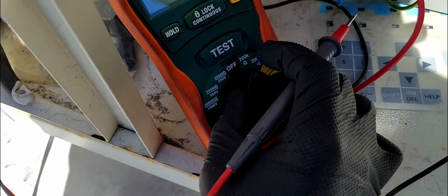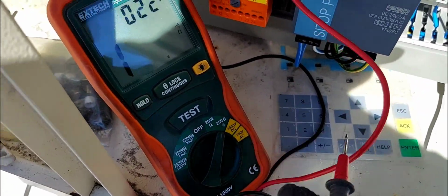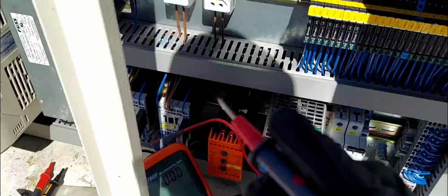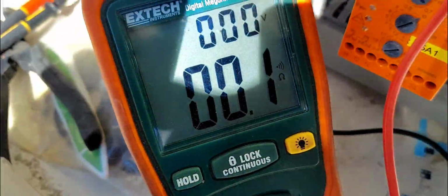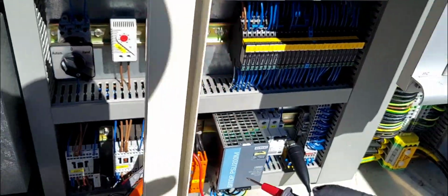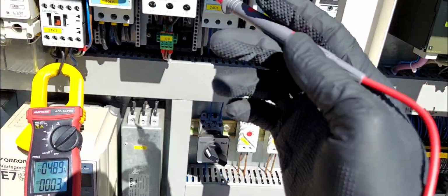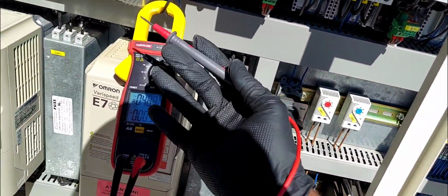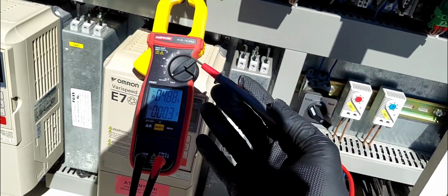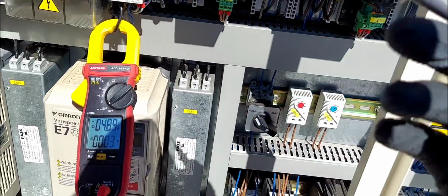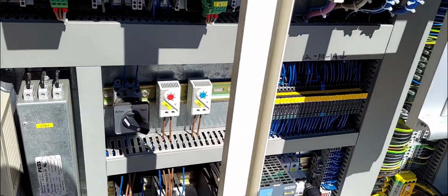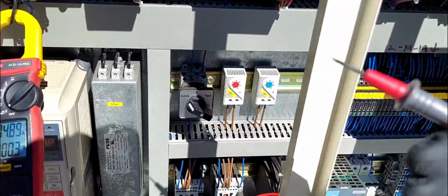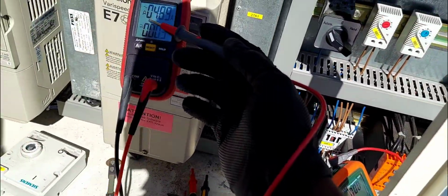All right. If it was shorted, I'll get something like this. Oh, my meter just turned off. Go back. If it was shorted, I gotta find a good ground. Here you go, that's what I'll get. I like to do this because I don't want to burn my meter out sending 1,000 volts into this thing when it's already shorted, and I can use my regular ohm meter to detect the short. I want to use this only when the short is so minute that I need to send 1,000 volts out into the windings to check that against the ground. If it's a bad short, a regular meter like this could do it.